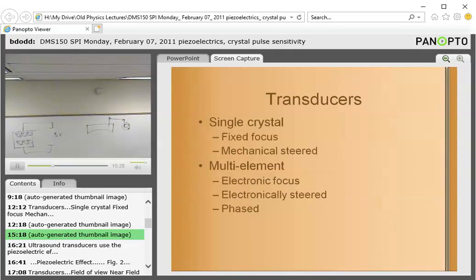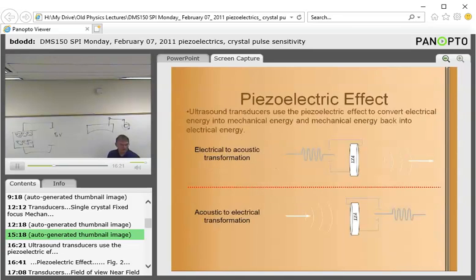Okay, so these transducers have multiple elements in them. Some of them that we have in the lab have as many as 512 crystals in it. Yeah, and that's not even the most you can get. Nowadays you can find these with 5,000 crystals in them. So there's a lot of different things coming out on the market. Most of them, like this one, will probably have at least 128, maybe 256 crystals in the head of this transducer. Okay, so they're getting better and better about making them. So these are electronically focused. We can actually change the focus, unlike the single crystal, like this one, which was focused at one place. The electronic ones we can focus at multiple places, and it uses a technique called phasing, and we'll get into that probably next week, what phasing is.